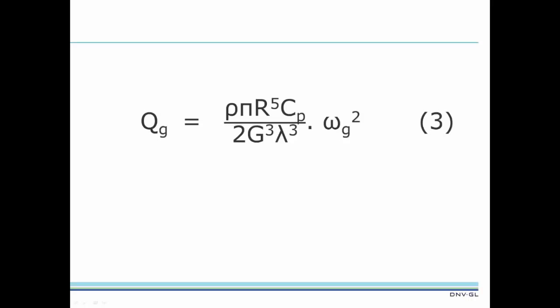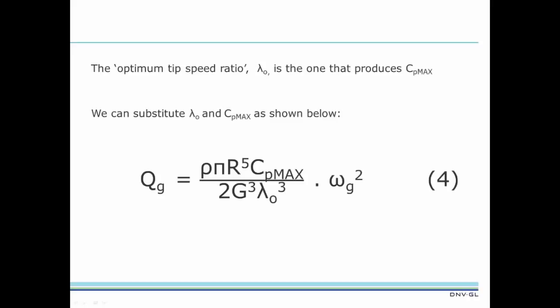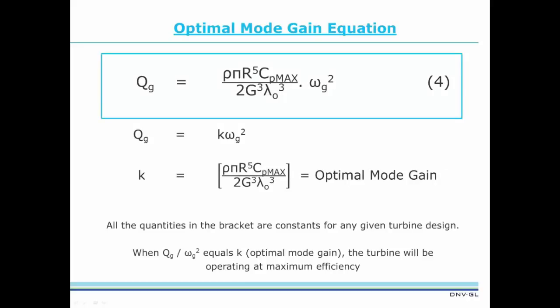The optimum tip speed ratio, lambda O, is the one that produces the maximum power coefficient, Cp max. If we substitute lambda O and Cp max into equation 3, we have the optimal mode gain equation. Equation 4 is the optimal mode gain equation. It shows generator torque proportional to generator speed squared. All the quantities in the bracket are constants for any given turbine design. The value of the bracket, K, is the optimal mode gain value. When the ratio of generator torque to generator speed squared equals the optimal mode gain value, the turbine will be operating at maximum efficiency.